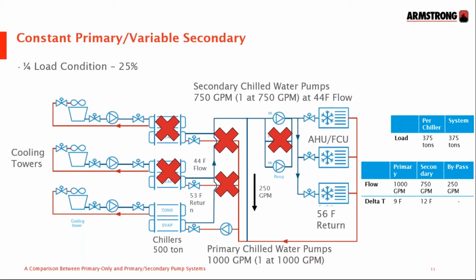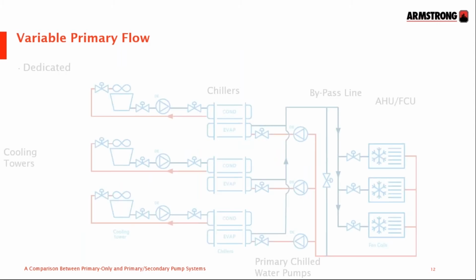So that's a constant primary, variable secondary: how the pumps and the chillers are sequenced in and out on the primary side, and how the secondary pumps are sequenced in on the secondary side. The number of pumps working on the secondary side have no bearing on what's happening here on the primary side. Let's look and see how variable primary flow works.